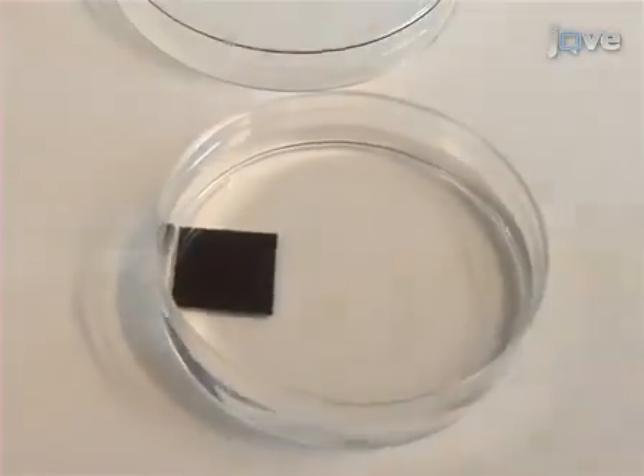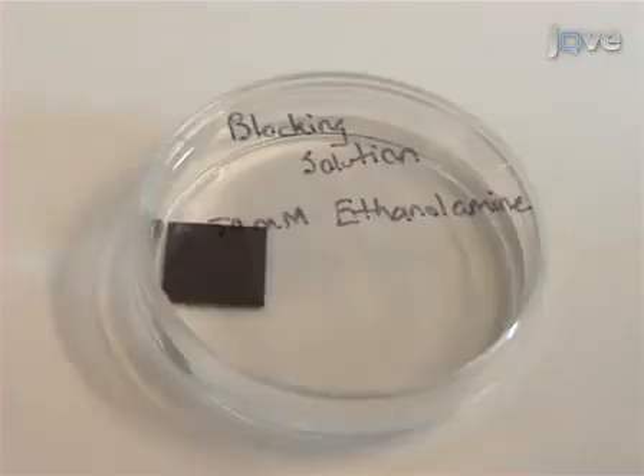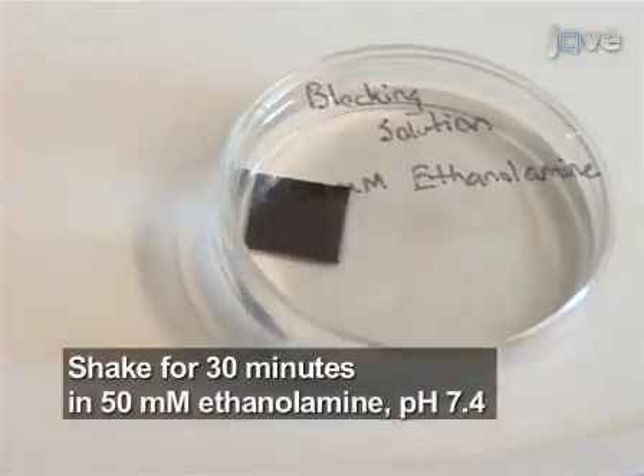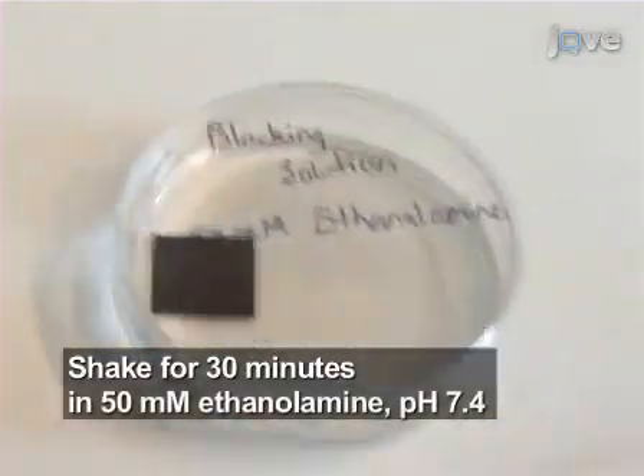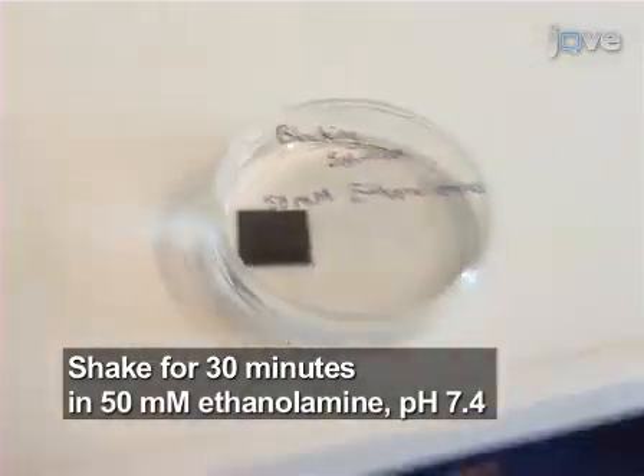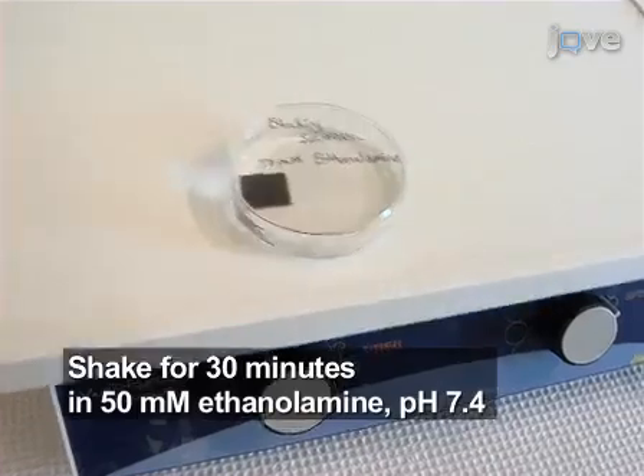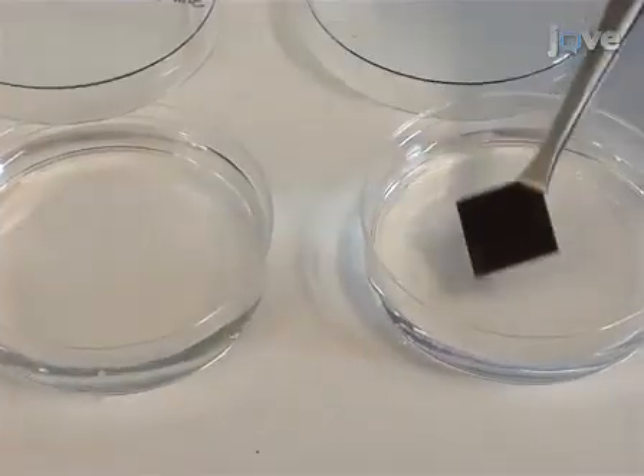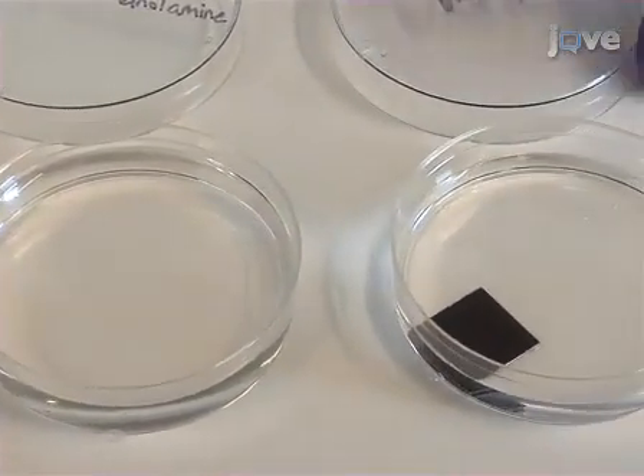Deactivate the remaining NHS groups on the copolymer surface by submerging the chips in a 50 millimolar solution of ethanolamine with the pH adjusted to 7.4 for 30 minutes while on a shaker plate. Thoroughly rinse the ethanolamine using PBS and then deionized water.